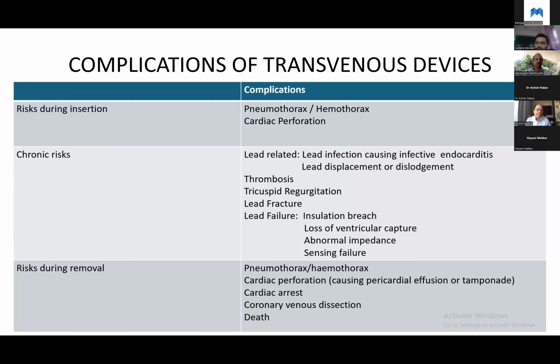All those situations can lead to problems if we are planning for upgradation or any other devices through the upper limb venous system. Another lead-related problem in transvenous ICD is lead fracture and lead failure. Lead failure is mainly related to insulation breach, and that may lead to an abnormal rise in impedance, an abnormal fall in impedance, or a rise in capture threshold, and sensing failure. That may lead to capture failure and inappropriate device function.